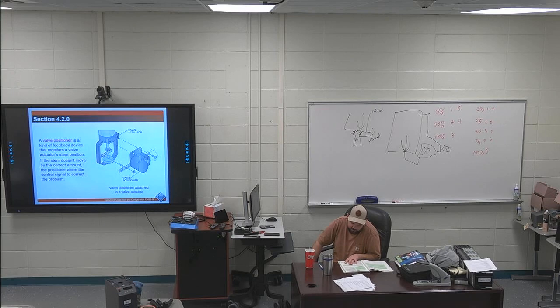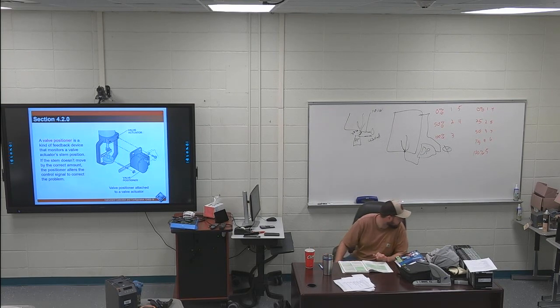Online test question, as shown in figure 18. The position of the mechanical link indicates the stem's position when compared to the incoming signal. If the two don't match, the positioner either increases or decreases the control signal to the valve diaphragm in order to bring the stem to the correct position.